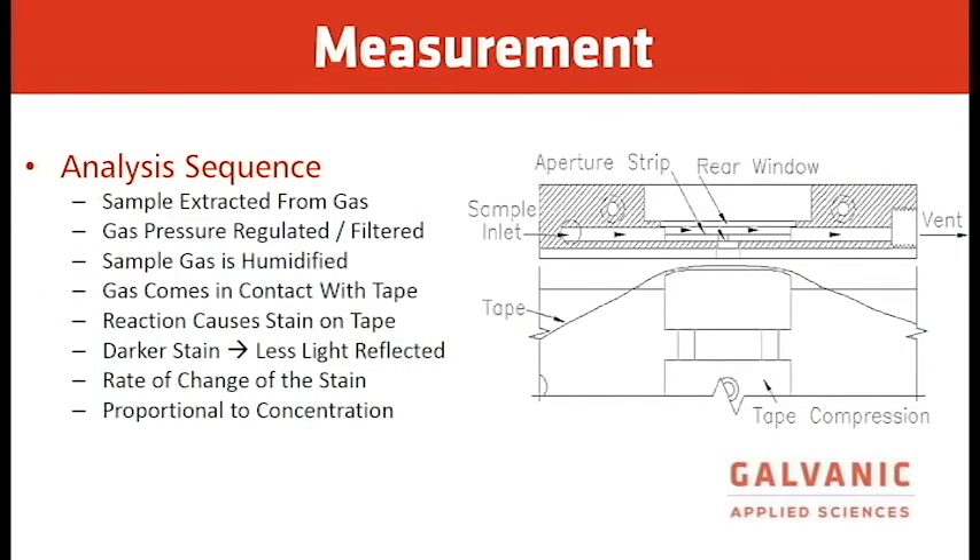For the analysis sequence: the sample is extracted from the gas, the gas pressure is regulated and filtered, the sample gas is humidified, the gas comes in contact with the tape causing a stain, the darker stain reflects less light back to the sensor block, the rate of change of the stain is measured, and the rate of change is proportional to the concentration.